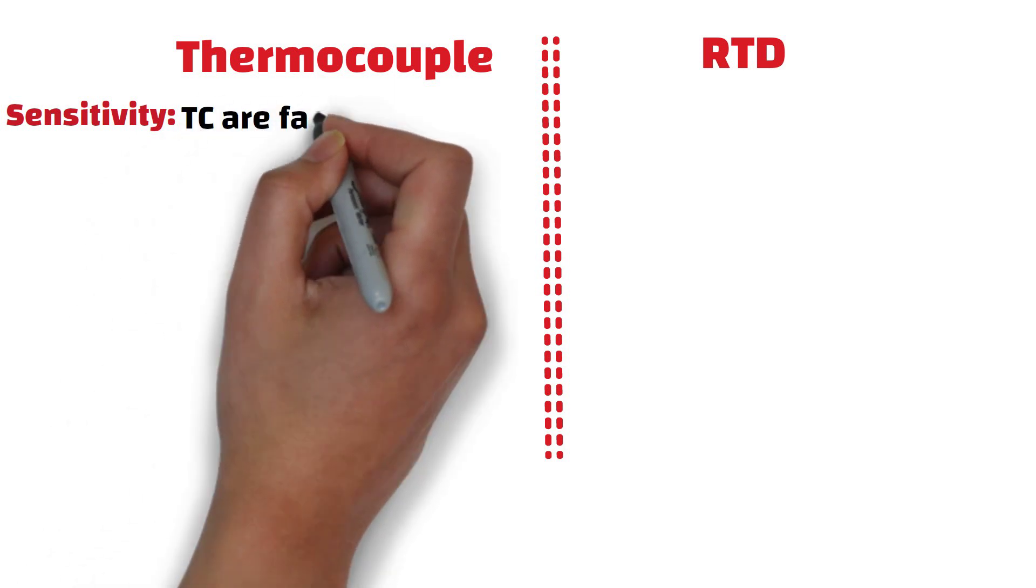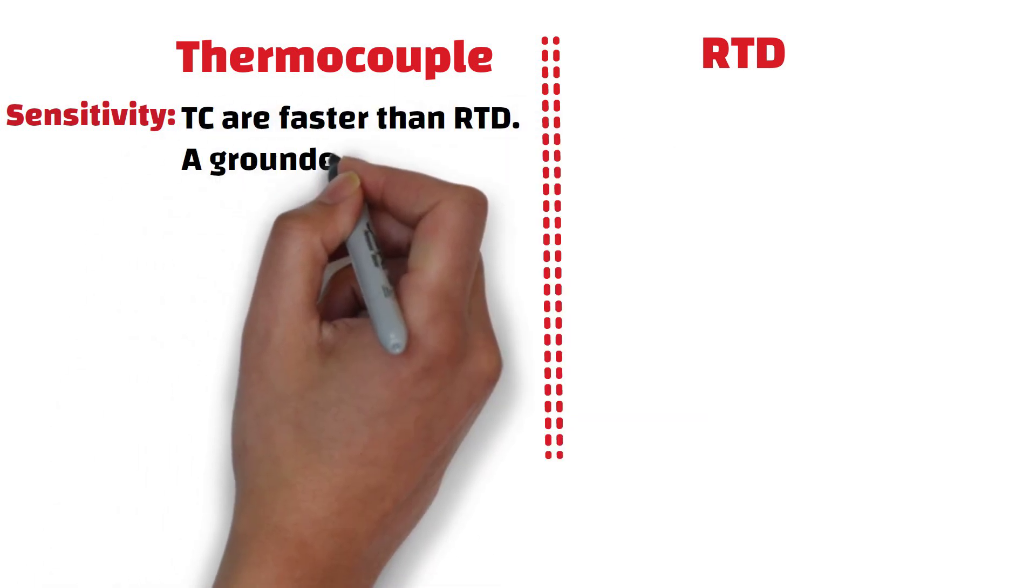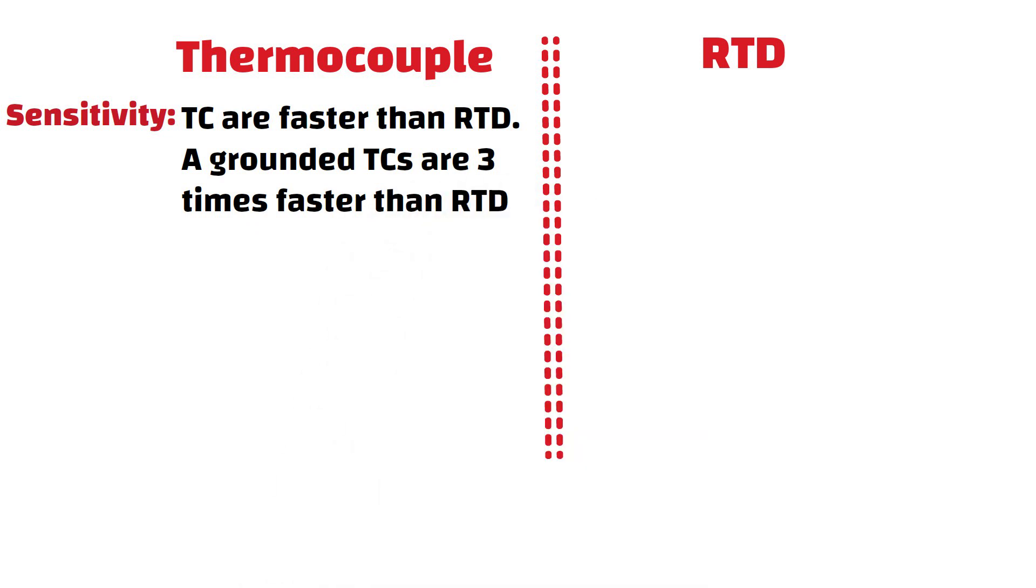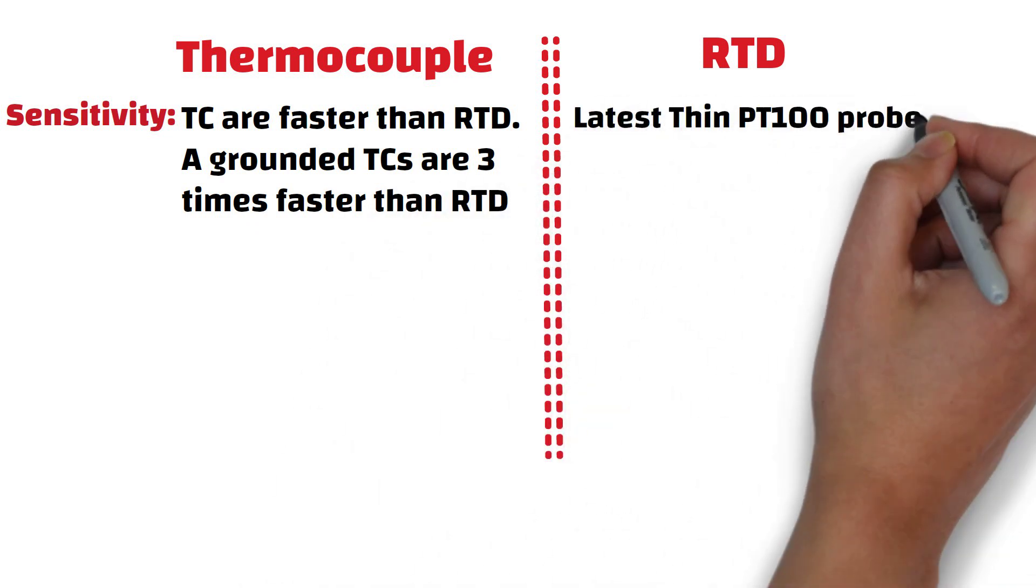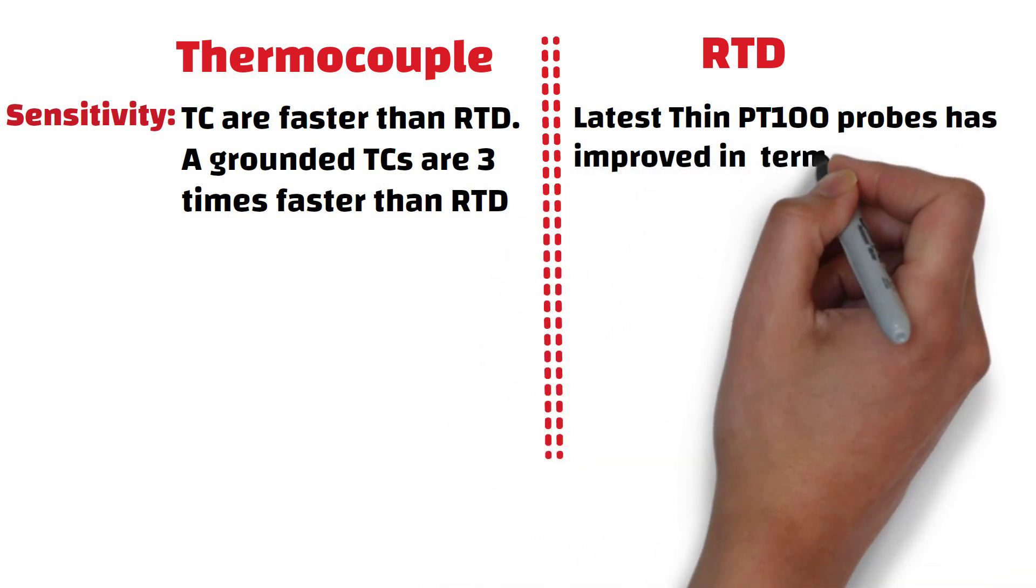In terms of sensitivity, thermocouples are much faster than RTD. For example, a grounded thermocouple are three times faster than RTDs. However, latest thin PT100 probe has improved in terms of response time.